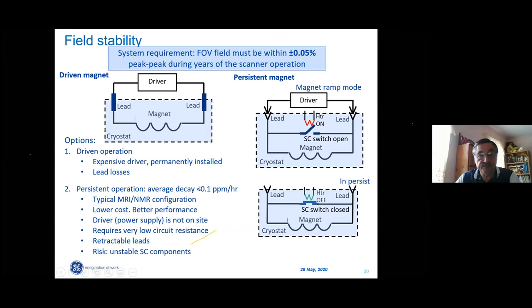Field stability. Again, the scanners require that magnetic field is within 0.1% of the nominal value. How do we do it? There are two options. The first is driven operation. We have a highly precise driver or power supply that is always connected. The disadvantages of this configuration are high losses in current leads, and availability of these highly stable drivers. They are first very expensive and by far less stable than this requirement.